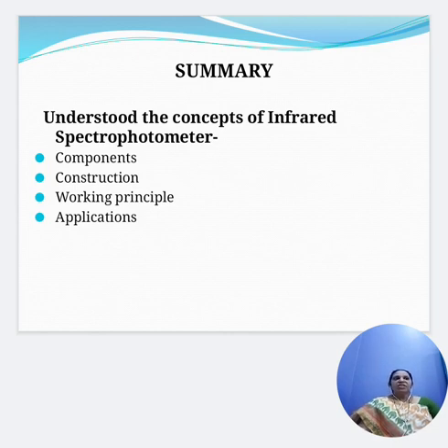Now the working of the infrared spectrophotometer: a beam of infrared light is produced from the light source, and when it is passed through the interferometer, it gets split into two separate beams. One is passed through the sample and another one is passed through the reference chamber. The beams are both reflected back towards a detector. However, first they pass through a chopper which quickly alternates which of the two beams enters the detector, and which converts a change in the incoming infrared light to electrical energy.